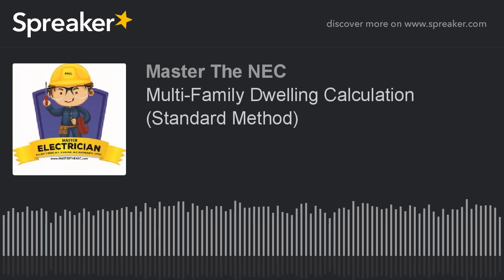All right? Now, that's just a general rule. There are other caveats to remember when you're paralleling and how you size the grounded conductor when you parallel. We're not going to go into all those because I do teach you that in another application, but you have to keep all those things into consideration when you're paralleling. In other words, I can't parallel smaller than 1/0. So if I end up paralleling my grounded conductors, I have to remember that they can't end up being smaller than a 1/0. But I can parallel my grounded conductors as well.